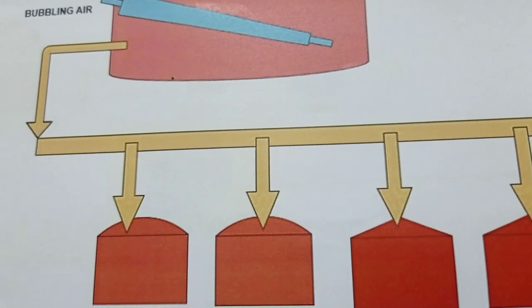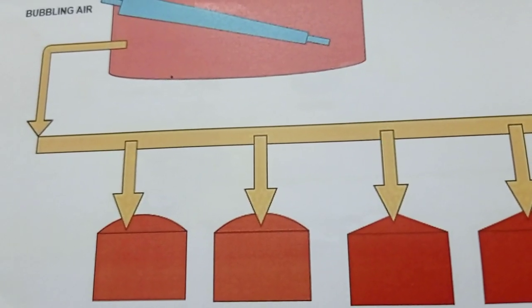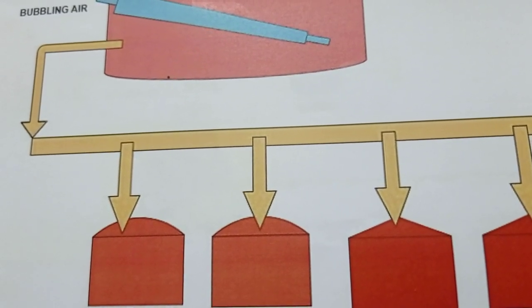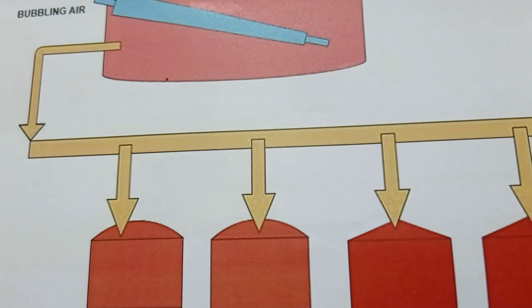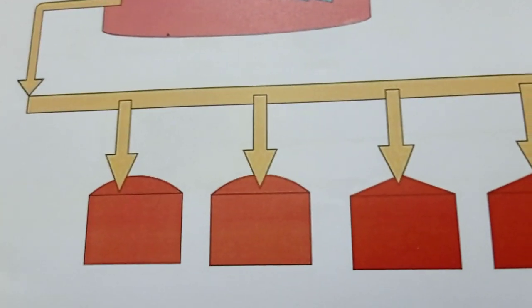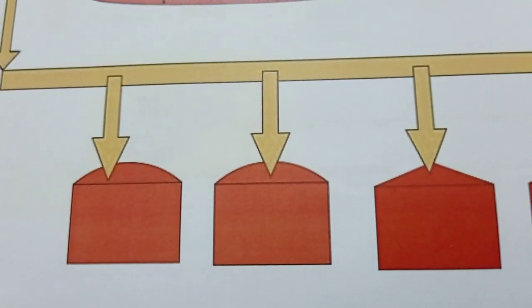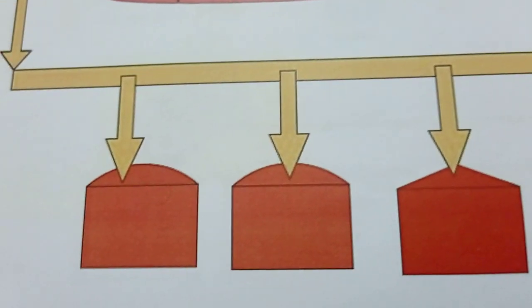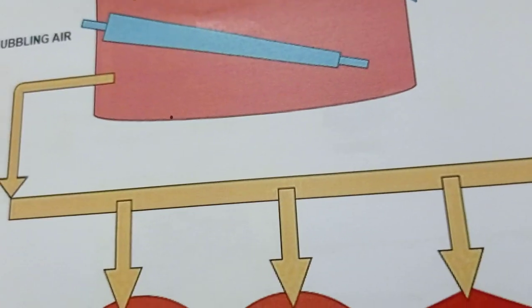When you use steam, what happens? It reduces the oxygen, and soon the fire may get extinguished. But if you use water, a high amount of energy is generated and the tank may get pressurized. So it's preferable to use steam instead of water. Okay, so this is all about sulfur handling and the sulfur method.